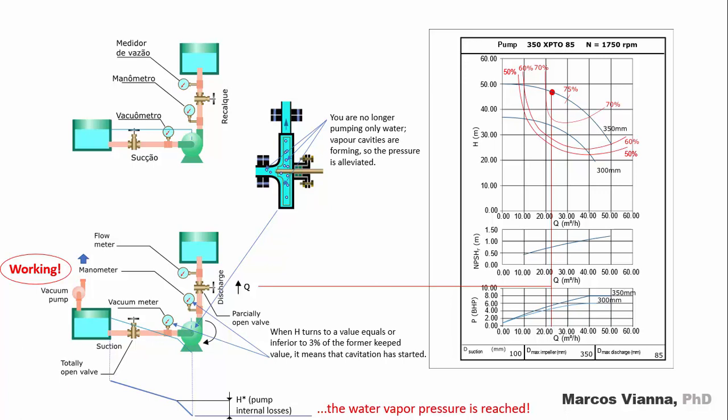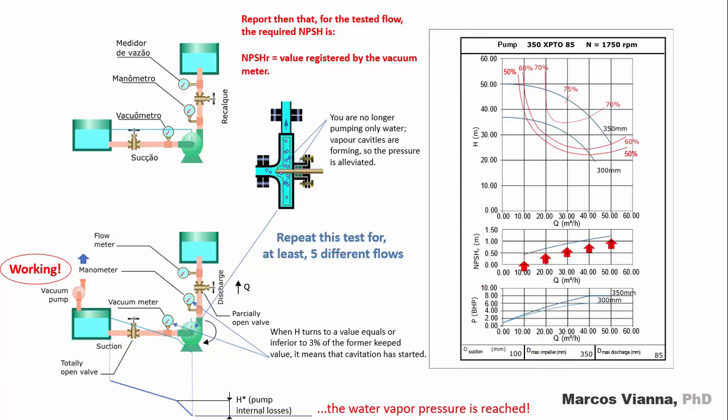Why? Because from now on, you are no longer pumping only water. Vapor cavities are forming, so the pressure is relieved. Now we can write down in our report that for the tested flow, the required NPSH is equal to the value registered by the vacuum meter. Repeat this test for at least 5 different flow values. That is how we get the NPSHR curve that we wanted.